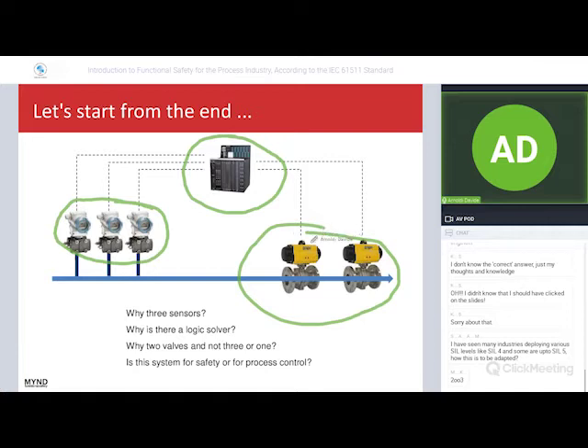2 valves. In the market there are a lot of valves, very reliable, but I would like to be sure about the closure of the line. So, from my experience, I install 2 valves because 2 is better than 1. This is not a justification. We need to prove and demonstrate why we have to install 2 valves instead of 1. 2 valves are very expensive compared to 1.